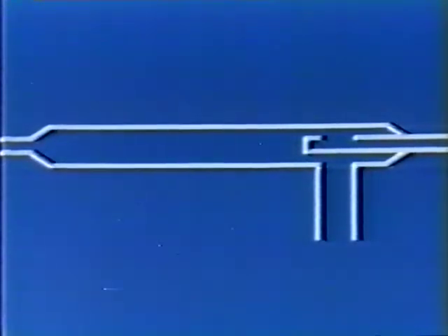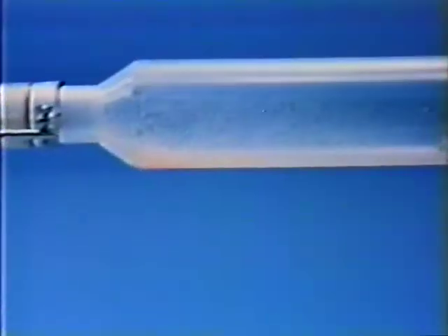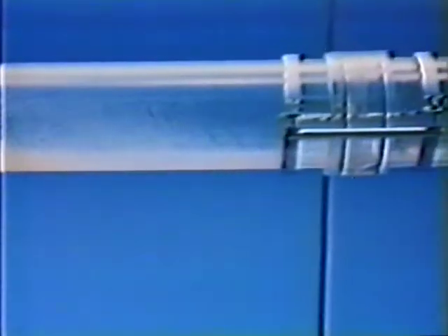Its operation is based on locally lowering the gas velocity, causing the annular flow in the line in the widened part to be converted into flow along the bottom of the pipe. The widened line portion must be so long that the gas stream entering at high velocity will have steadied down by the time it comes to the point where the liquid is separated from the gas stream.